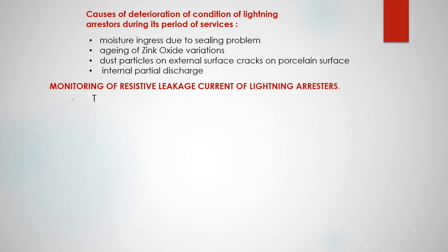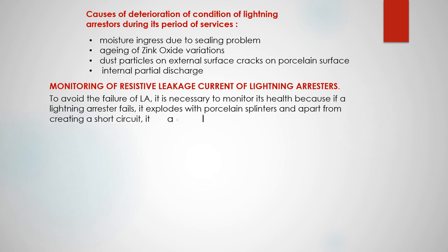Causes of deterioration of the condition of a lightning arrestor during its period of service: moisture ingress due to sealing problem, aging of zinc oxide varistors, dust particles on the external surface, cracks on the porcelain surface, internal partial discharge.